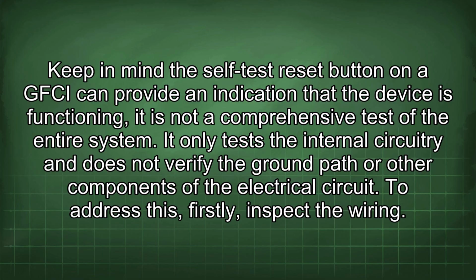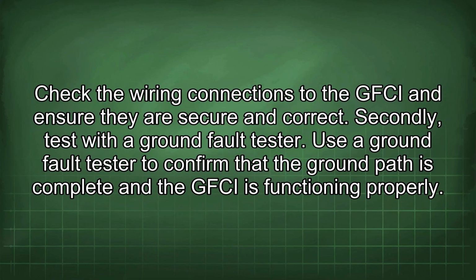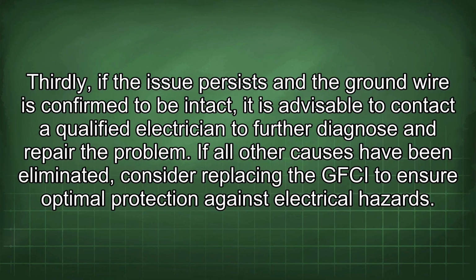To address this, firstly, inspect the wiring. Check the wiring connections to the GFCI and ensure they are secure and correct. Secondly, test with a ground fault tester. Use a ground fault tester to confirm that the ground path is complete and the GFCI is functioning properly. Thirdly, if the issue persists and the ground wire is confirmed to be intact, it is advisable to contact a qualified electrician to further diagnose and repair the problem. If all other causes have been eliminated, consider replacing the GFCI to ensure optimal protection against electrical hazards.